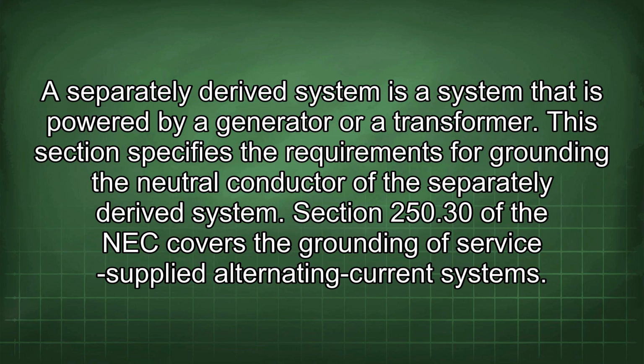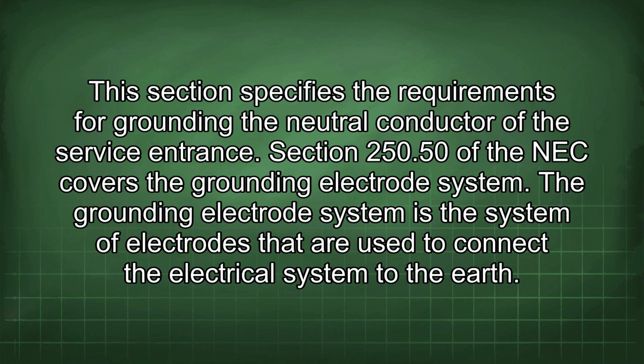This section specifies the requirements for grounding the neutral conductor of the separately derived system. Section 250.30 of the NEC covers the grounding of service-supplied alternating current systems. This section specifies the requirements for grounding the neutral conductor of the service entrance. Section 250.50 of the NEC covers the grounding electrode system. The grounding electrode system is the system of electrodes that are used to connect the electrical system to the earth.